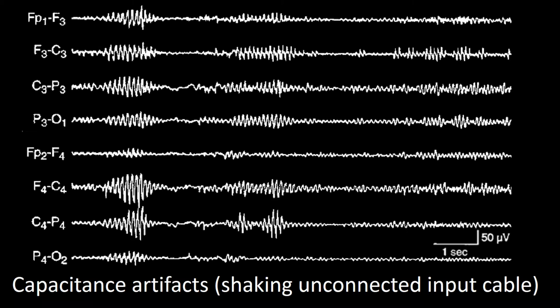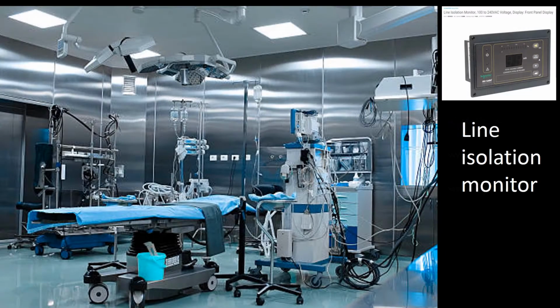This is an example of capacitance artifact resembling brain activity produced by touching the input cable, even when the input cable was disconnected from a patient. You can imagine how many potential artifacts can occur in an OR. One of them is not to be forgotten, which is the one produced by line isolation monitors. This is a machine that is often used to measure leakage from the electrical sockets. And at times it is forgotten in the OR and it produces a significant amount of 60 Hz artifacts.